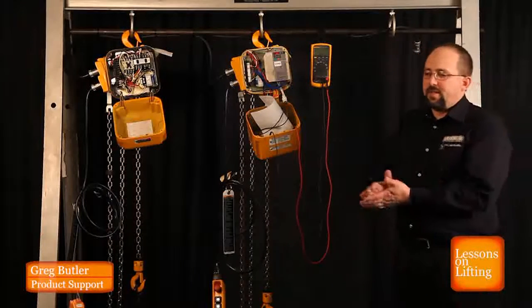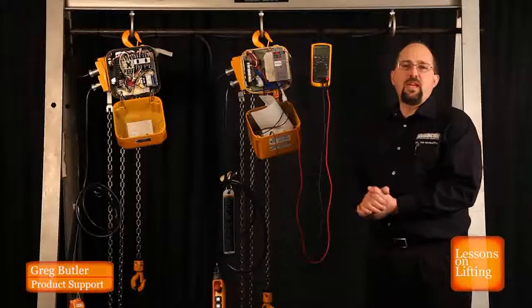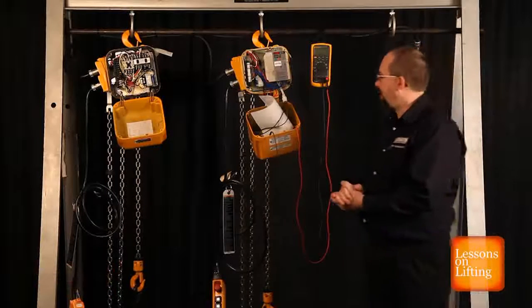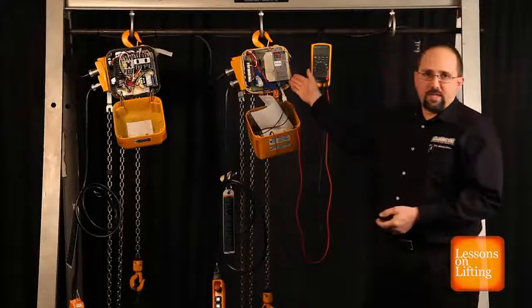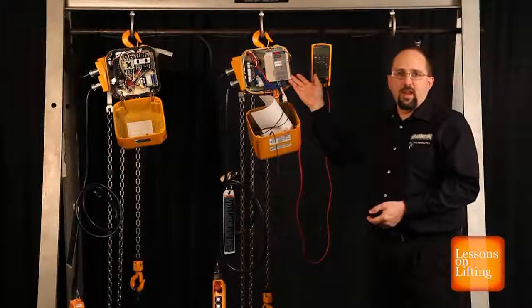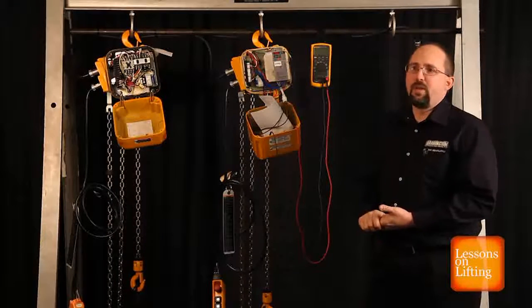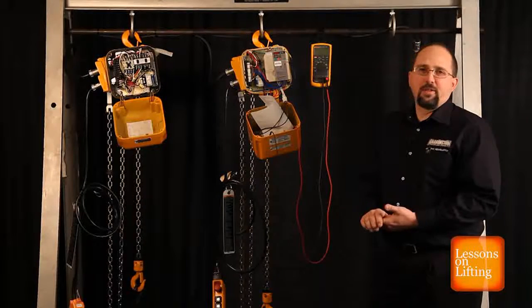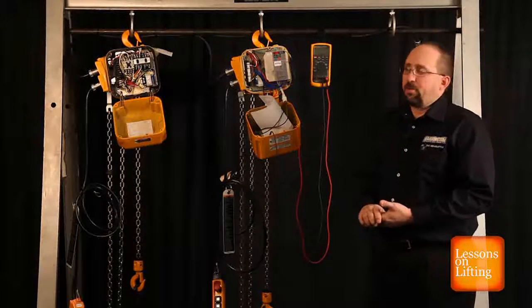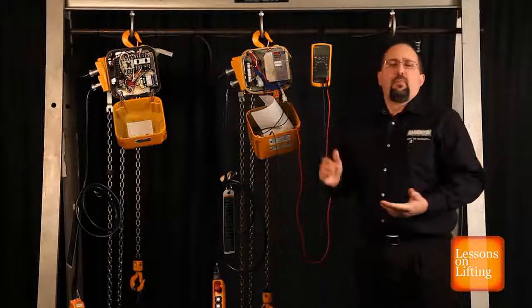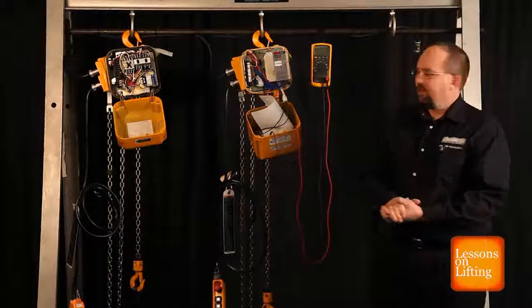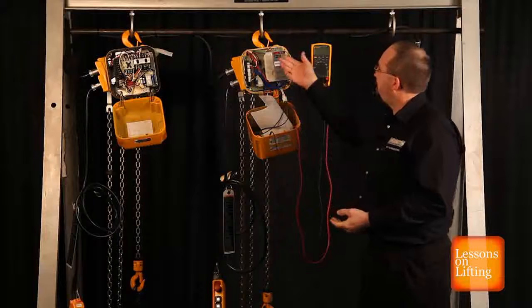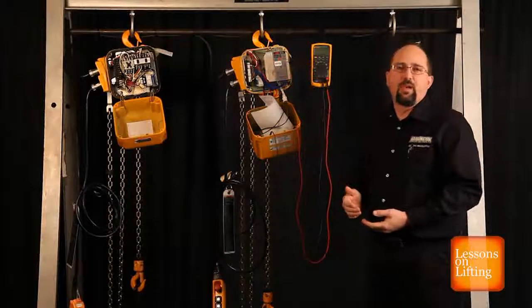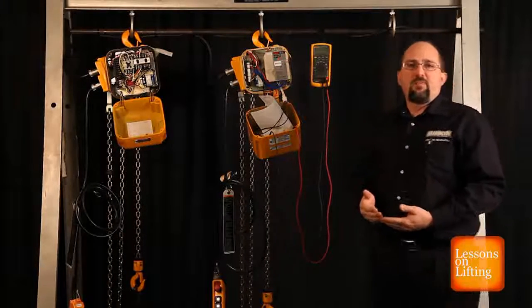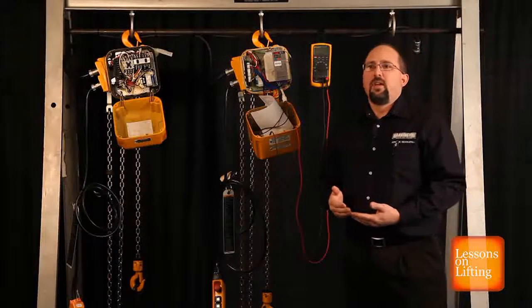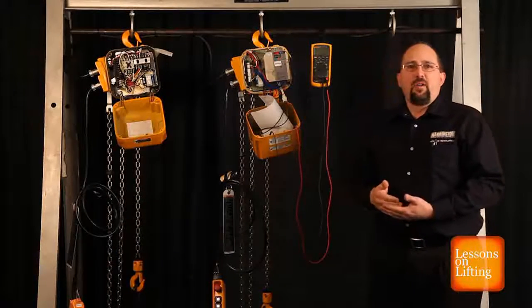Today we're going to talk about the HBB code on our drives. The under the cover VFD on Harrington ER2 and MR2 style hoists and trolleys has proven to be very reliable, but occasionally we do get calls, and the most common of those calls is, hey, my hoist has an H66. Well, actually, it's HBB. It stands for Hardware Base Block, and that code means that the VFD is not getting a signal from the e-stop button on the pendant.